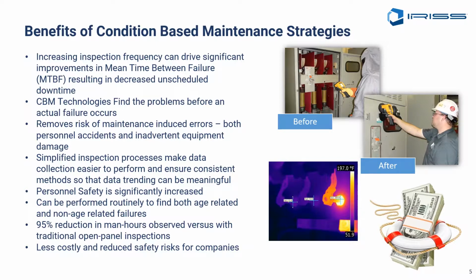You're increasing the safety of your personnel. We're not putting people at risk. You see these pictures here in the upper area of this slide - this guy's got his full arc flash suit on, but he's doing the work with an open panel. That's inherently risky and dangerous. In the middle picture, we have someone working through a safety device, taking infrared imaging, and can do ultrasound through similar devices, listening into the equipment without ever having to crack the door. He doesn't have to wear anything in terms of incremental PPE. So he's not working in an uncomfortable manner, and he's frankly isolated from the hazard. He's safer by doing it in this fashion.